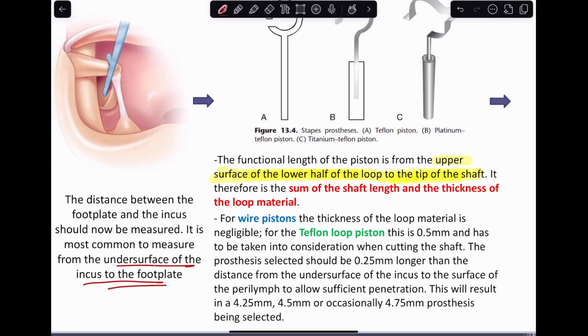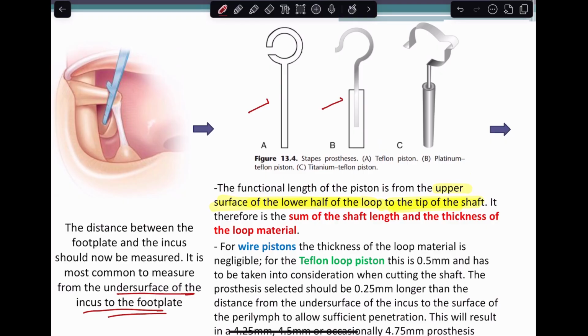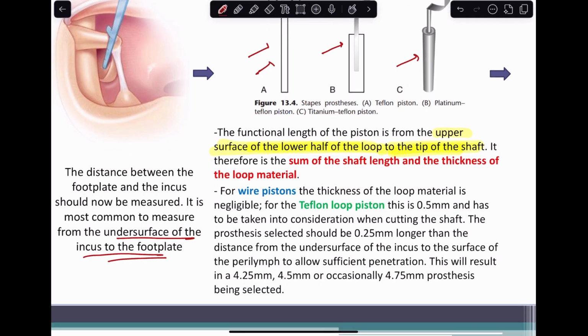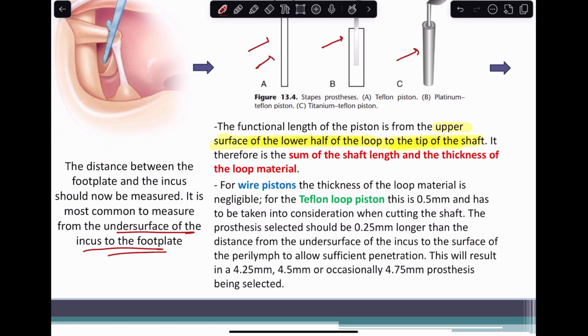So this is what a prosthesis usually looks like. These are some examples. The first one is a Teflon piston, the second one is a platinum Teflon piston, and the third one is a titanium Teflon piston. Now once we have measured the length of the piston, for a wire piston the thickness of the loop material is very negligible, so that is not taken into account. But in case of a Teflon loop piston, the thickness of the loop material is about 0.5 millimeter, and this has to be taken into consideration when we are cutting the shaft.